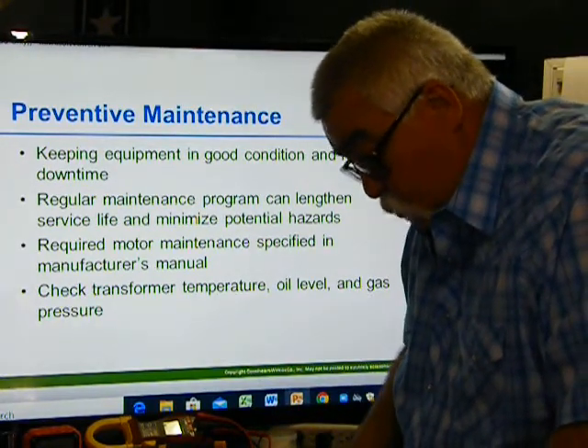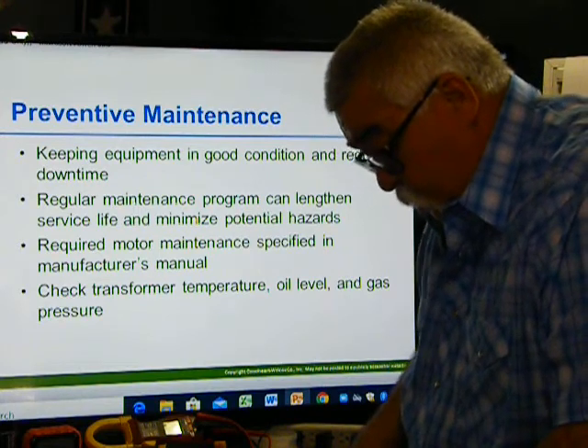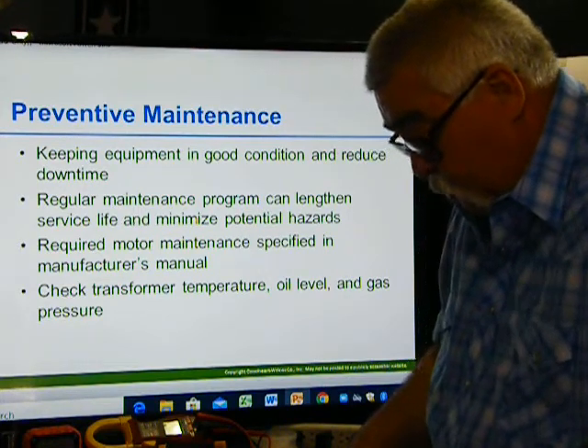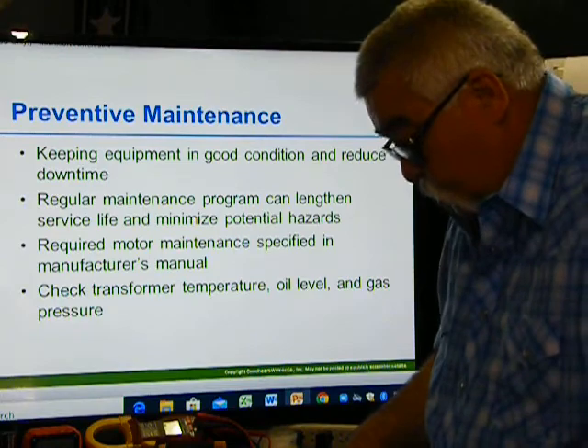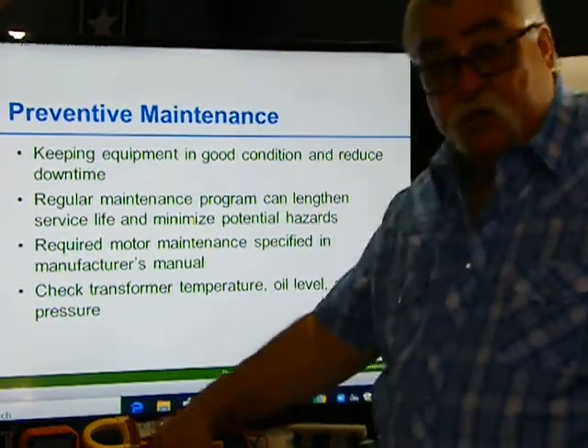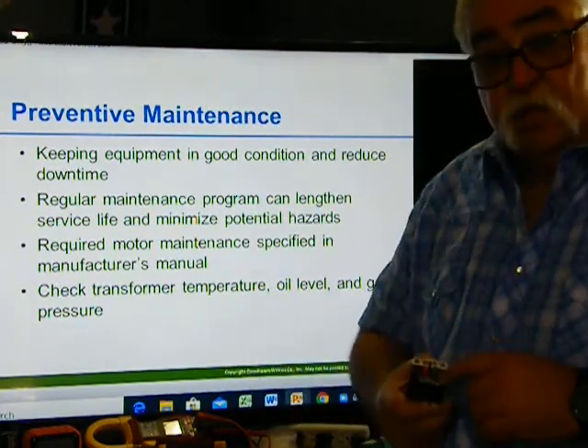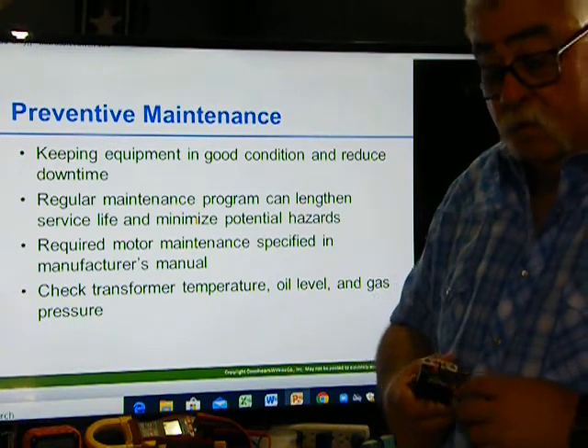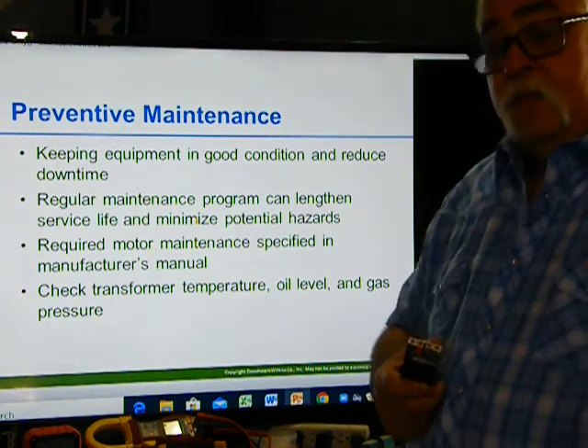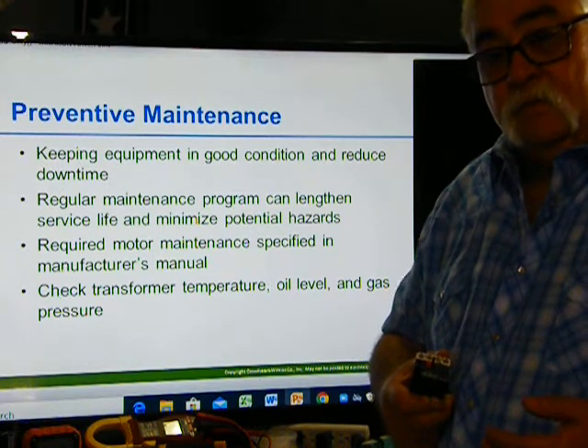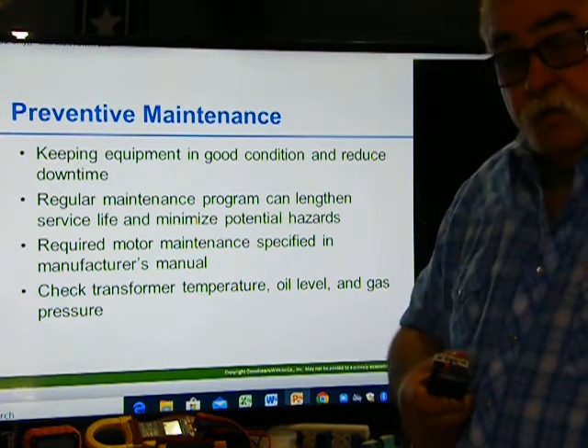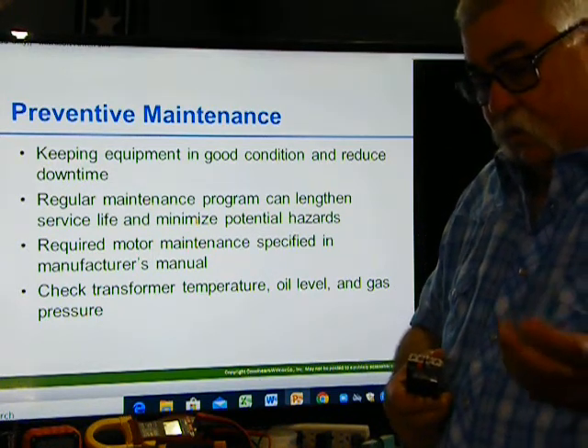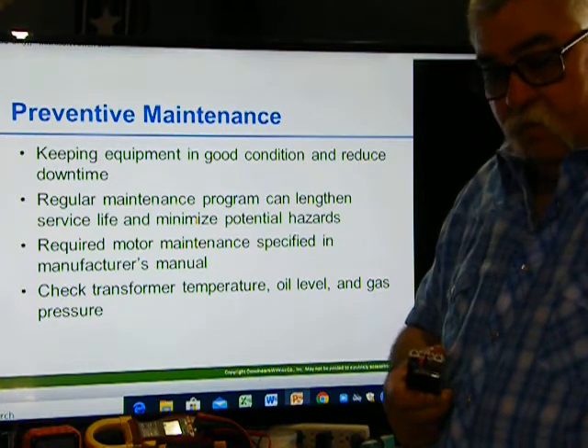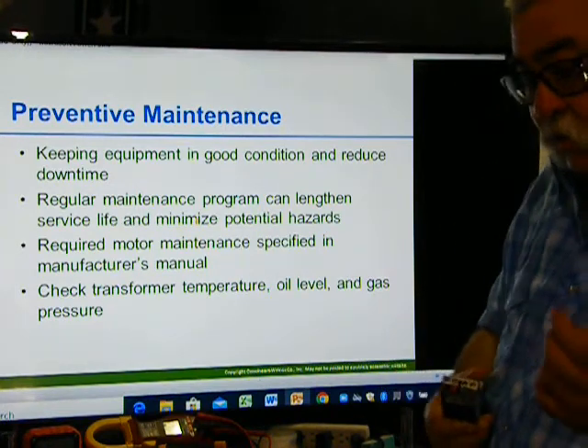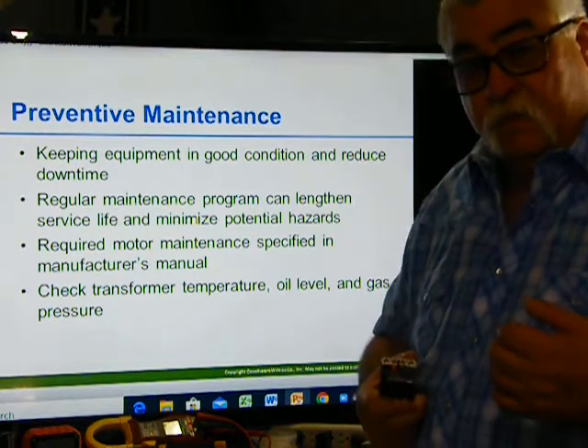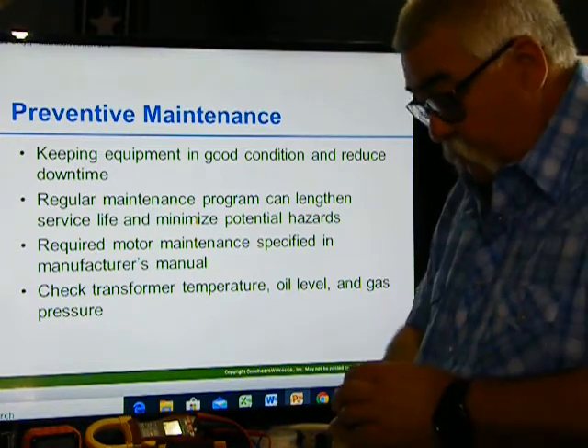And in the motor controls, we want to make sure to keep the motor controls clean, test moving parts, and contactors regularly. Overload relay settings should also be checked. So, make sure the settings are set to the motor. So again, if it's 1.15 or greater, 125%, the 40 degree Celsius temperature rise, 125%; all of the other motors is 115%.